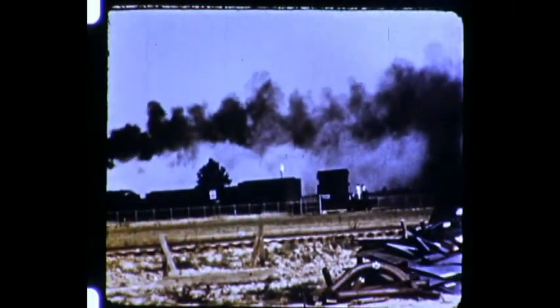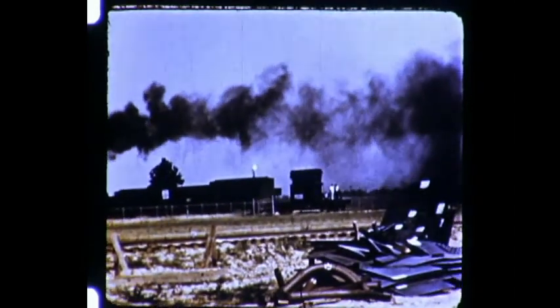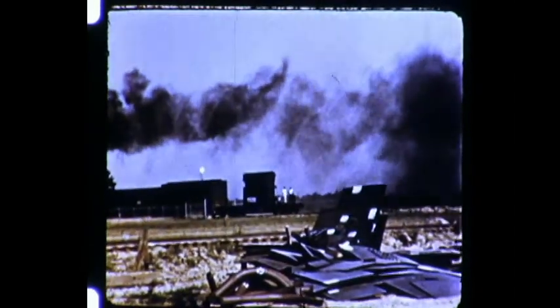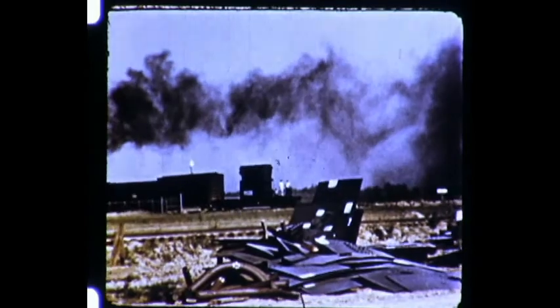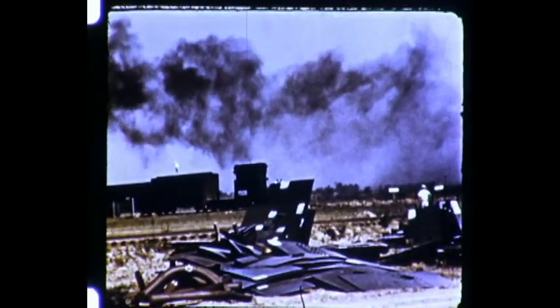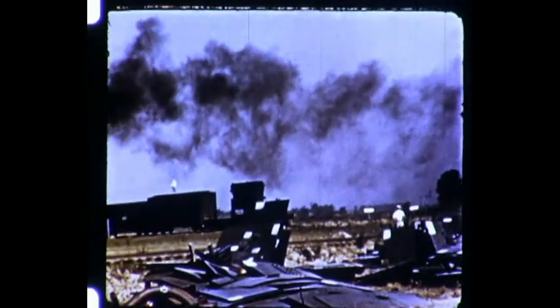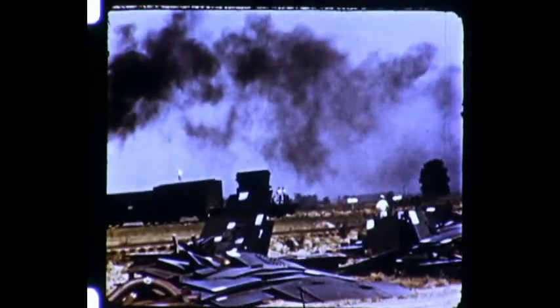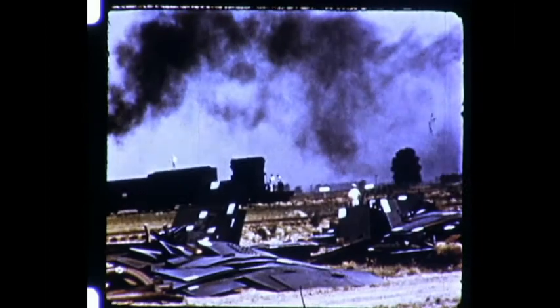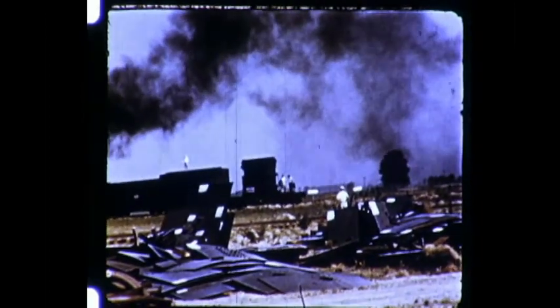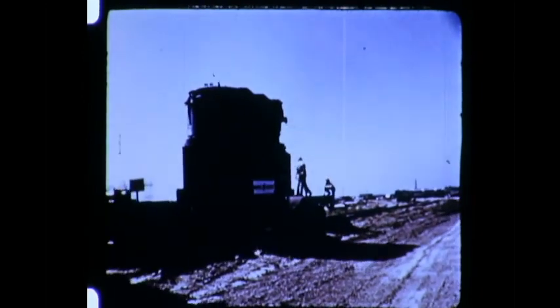Using water from this artificial lake fed from the nearby Sunflower River, the new station will have the most modern equipment available to serve its customers. And here comes an important piece of that equipment now. Arriving on a drop frame flat car is main power transformer number 2, a General Electric forced oil air-cooled unit rated 135,000 kVA, which will step up generator voltage of 13.8 kV to 115.5 kV.